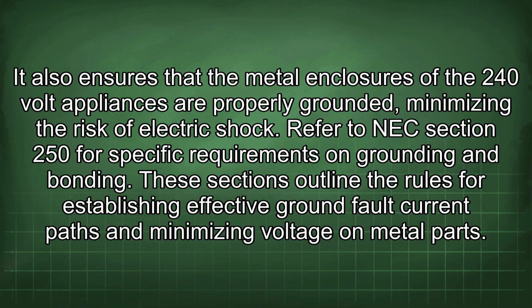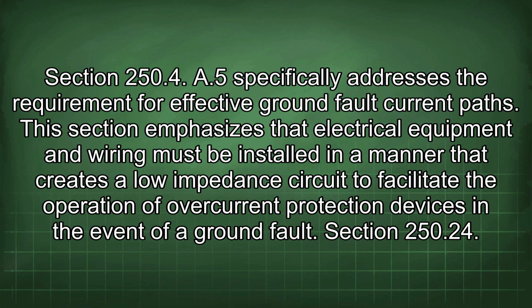Refer to NEC Section 250 for specific requirements on grounding and bonding. These sections outline the rules for establishing effective ground fault current paths and minimizing voltage on metal parts. Section 250.4(A)(5) specifically addresses the requirement for effective ground fault current paths. This section emphasizes that electrical equipment and wiring must be installed in a manner that creates a low impedance circuit to facilitate the operation of overcurrent protection devices in the event of a ground fault.